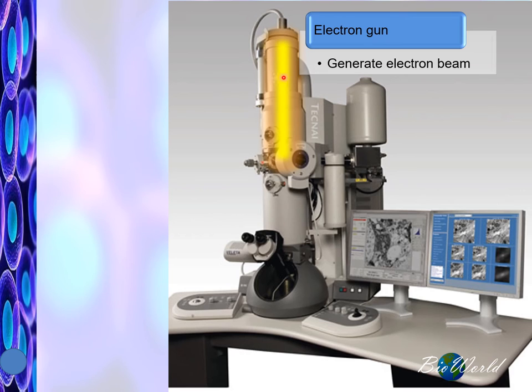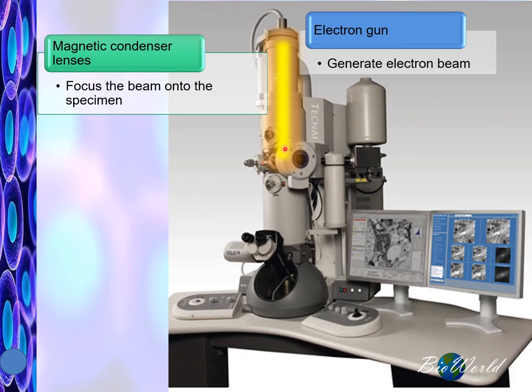That is why the column must remain a vacuum. This is to ensure that the electrons do not collide with the gas molecules and become diverted. To ensure that the electron beam travels directly to the specimen, this column will contain magnetic condenser lenses to help focus the beam.